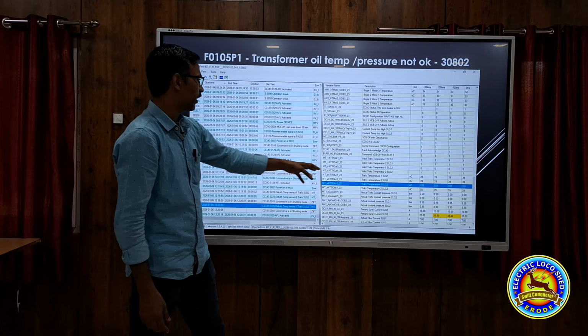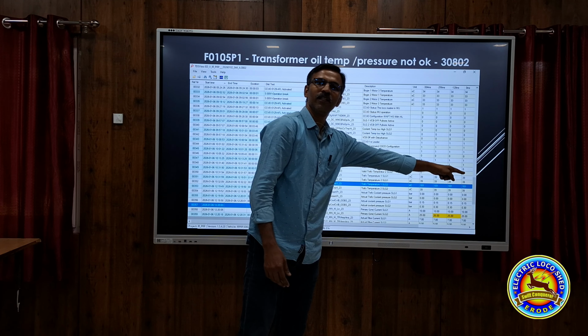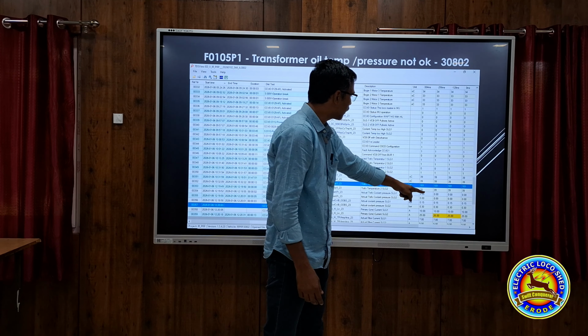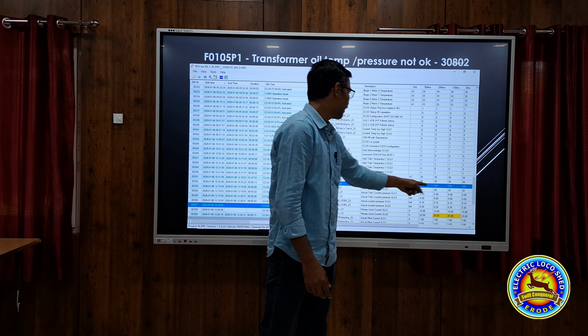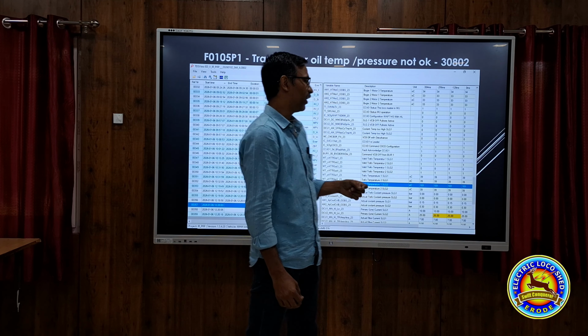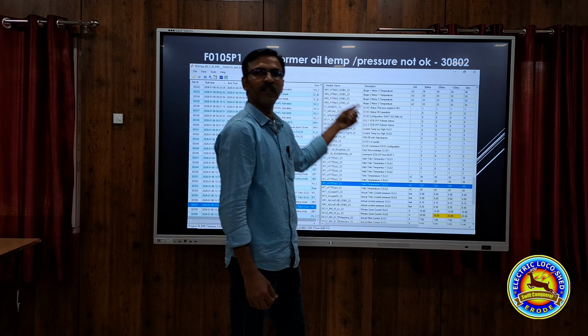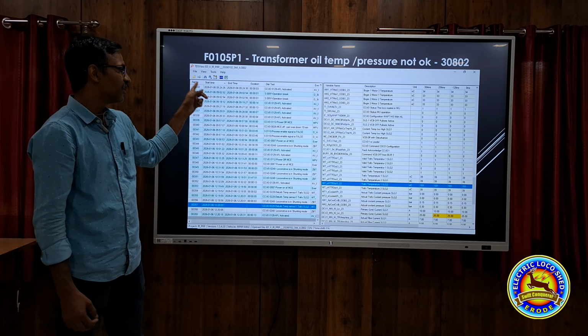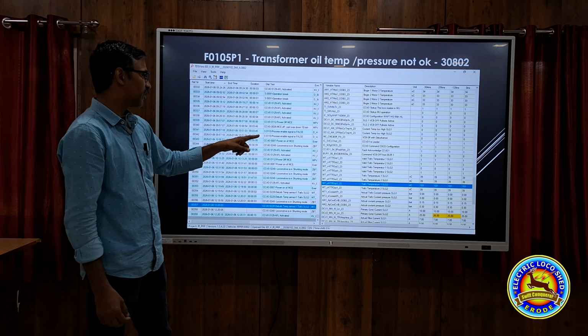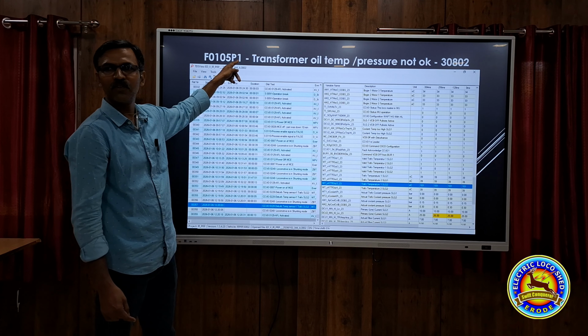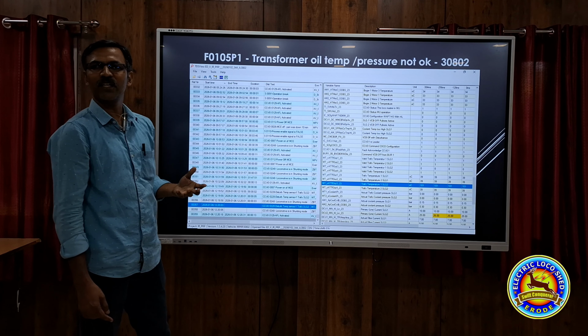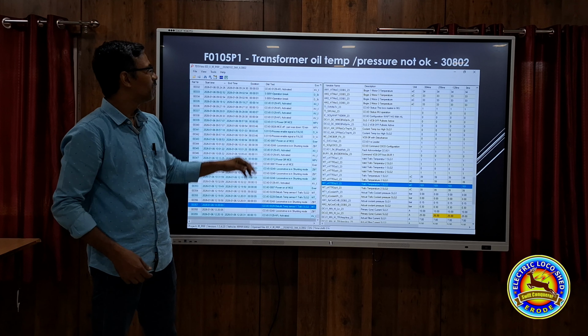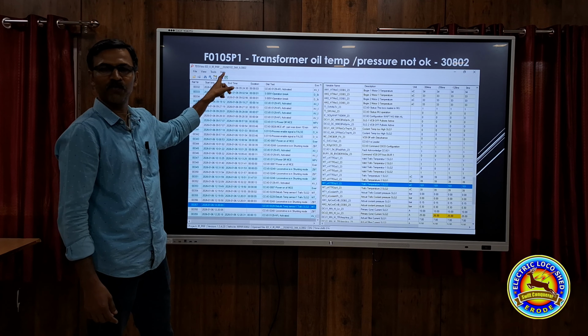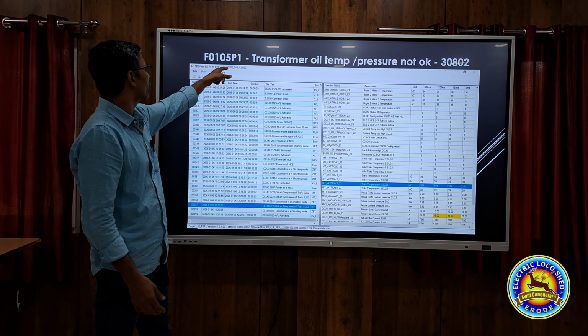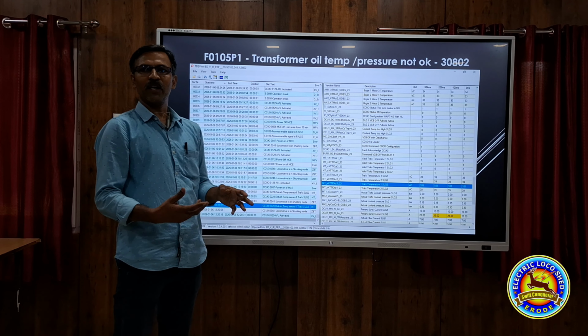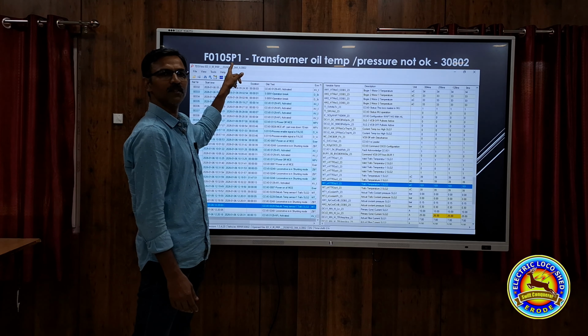In the same loco, in another occurrence, you can see the temperature was going beyond that level. All other sensors are saying 39, that is the actual value, but in this case this one was showing 101. In this case also, this message popped up. This was the problem, because if it was shown as a P2 fault, the loco pilot would not get confused. He would just acknowledge and continue. Nowadays many loco pilots know the problem, so most of the problems will be avoided. But recently one loco failed on account of this P1 and P2 confusion.